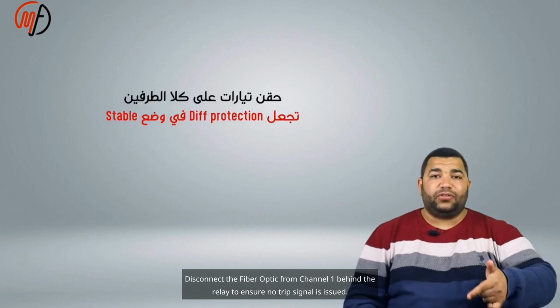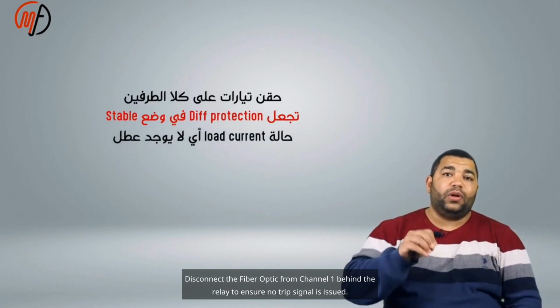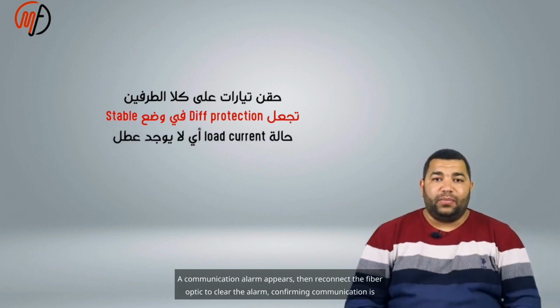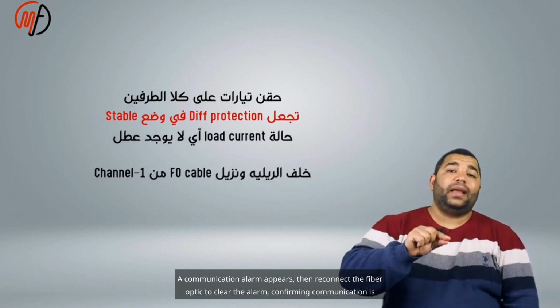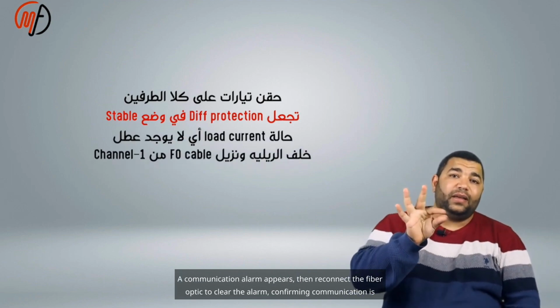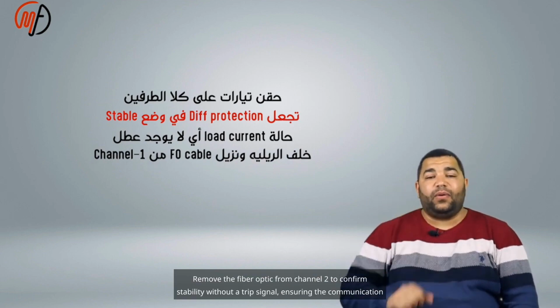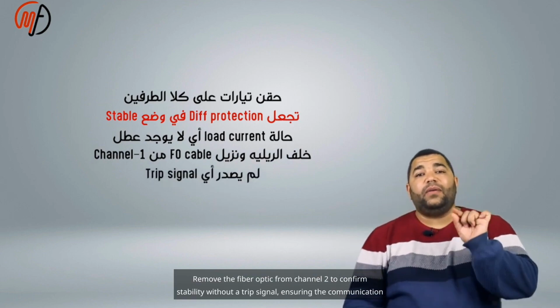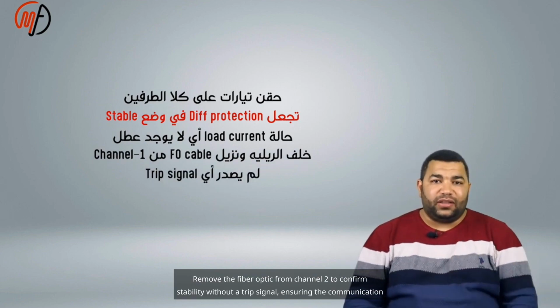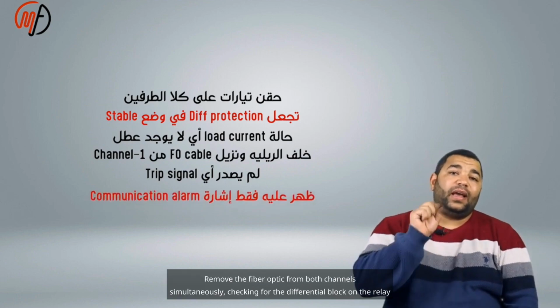Disconnect the fiber optic from channel 1 behind the relay to ensure no trip signal is issued. A communication alarm appears, then reconnect the fiber optic to clear the alarm, confirming communication is healthy. Remove the fiber optic from channel 2 to confirm stability without a trip signal, ensuring the communication alarm reappears.